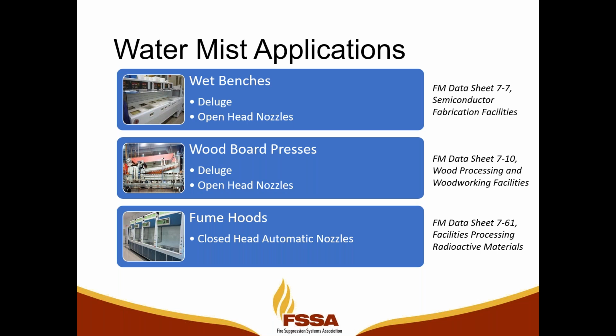And then finally, fume hoods. This is a negative pressure environment that's enclosed on all sides, but it's got a movable polycarbonate or glass window that allows a technician to get their hands in there and work with materials that have off-gassing or other noxious substances being given off that we want to suck out through an exhaust system. And in the case of fume hoods, we use automatic nozzles per FM's protection scheme. So again, there's a data sheet.